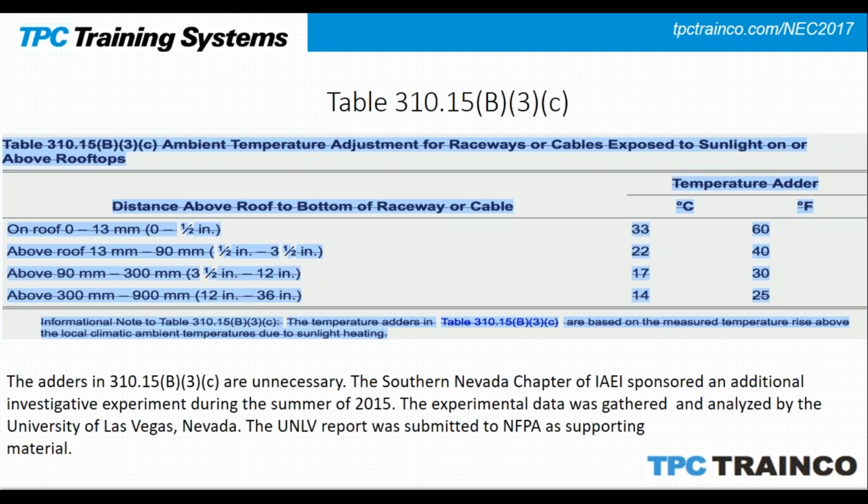Well, the Southern Nevada chapter of the International Association of Electrical Inspectors sponsored an investigation, and they found out that really there was no additional heating of conductors up on that roof. And so they submitted their data to the technical committee, and this table has now been deleted from 310.15. So it is no longer there. So we do not have to make an adjustment for conductors that are installed on roofs anymore.